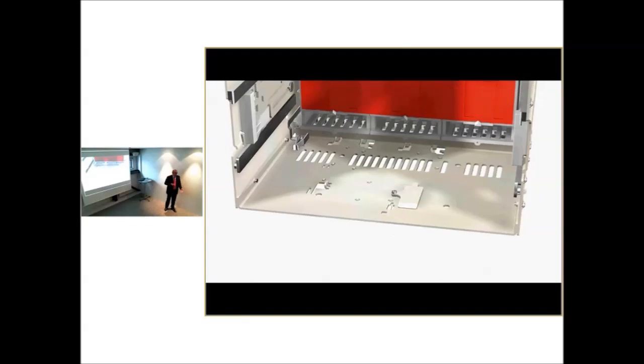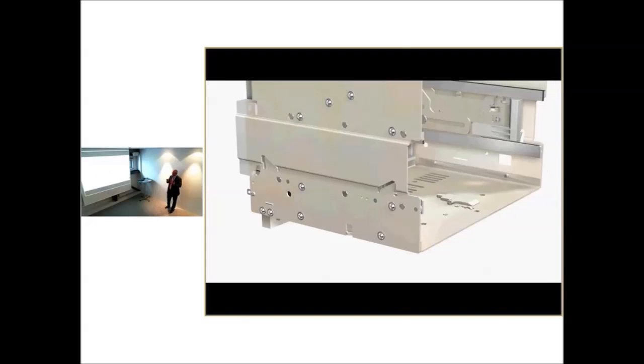You have a possibility not to insert the breaker when it's in open. You cannot open or close the door when the breaker is inserted in open position. And it was available already on Emax.